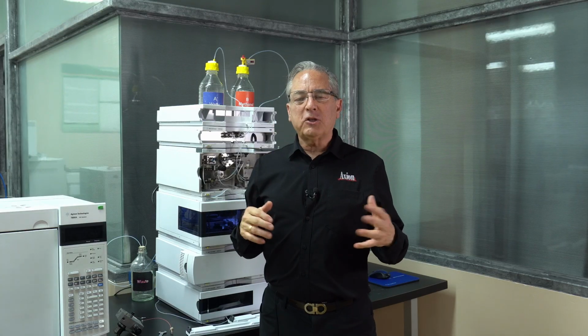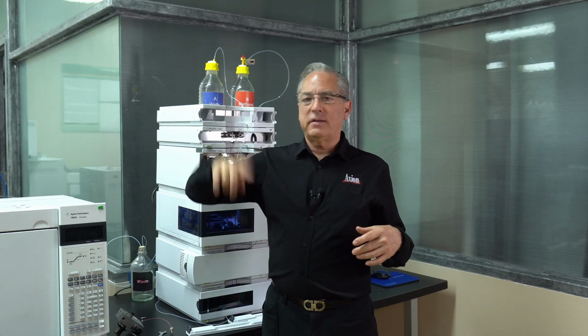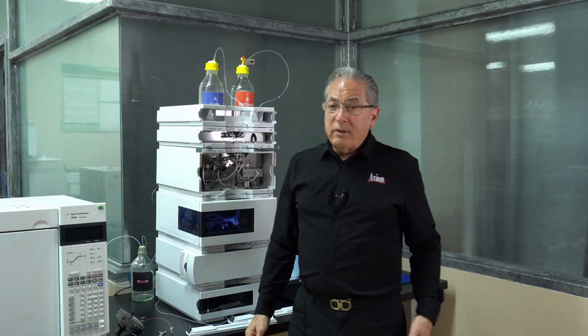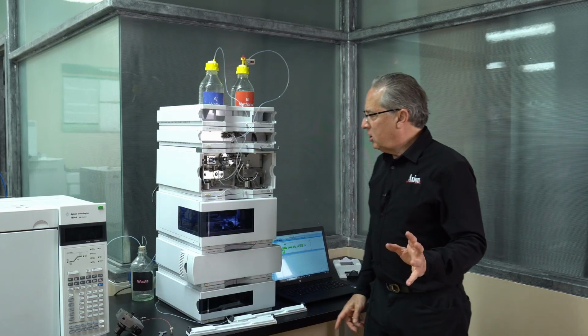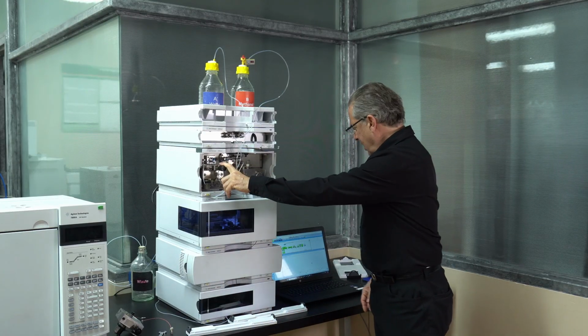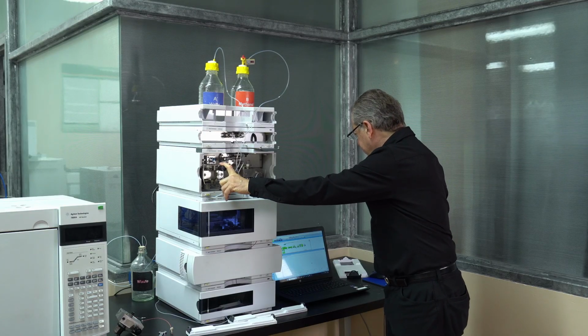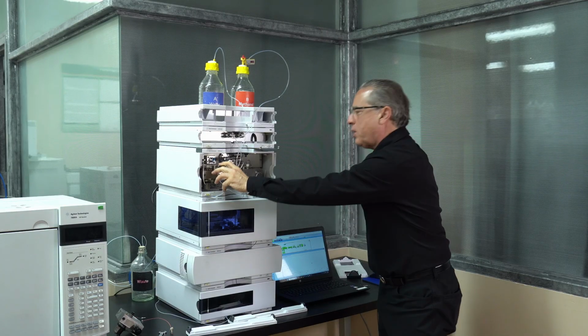So let's say the fluctuation is really big, going plus or minus 20 bar. You've probably got an air bubble. How do we cure that? I'm going to open the purge valve. Right now our pressure is 365 bar, or 354 bar.